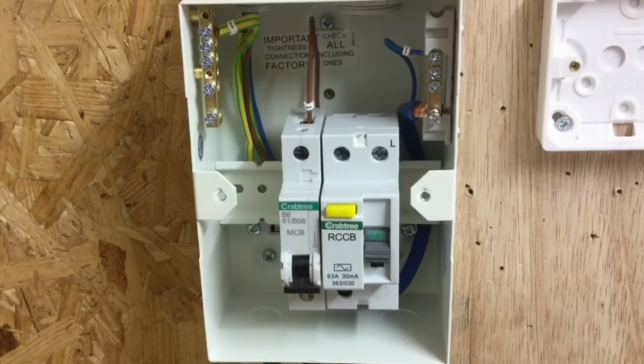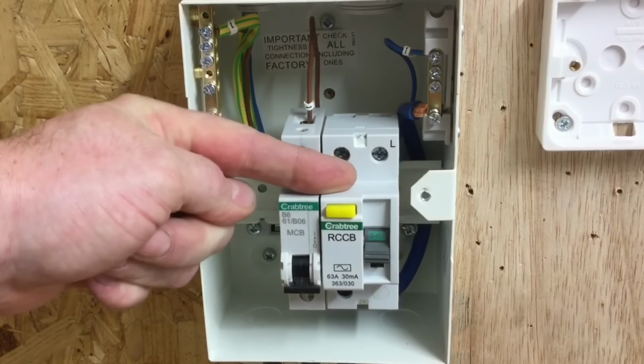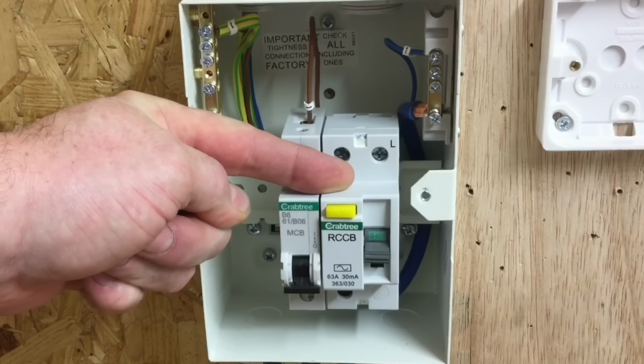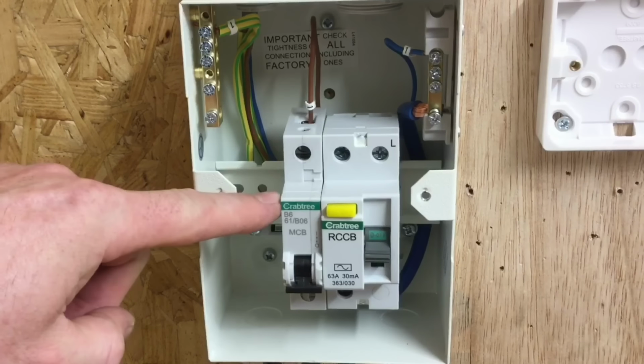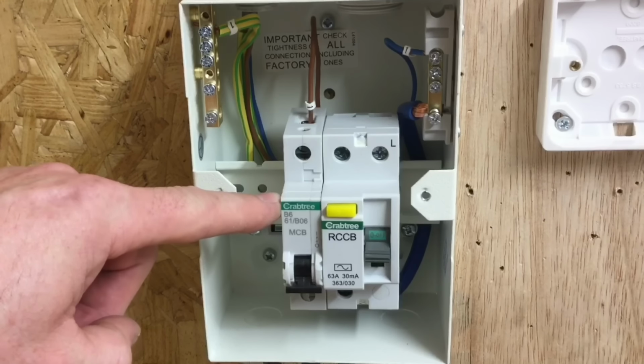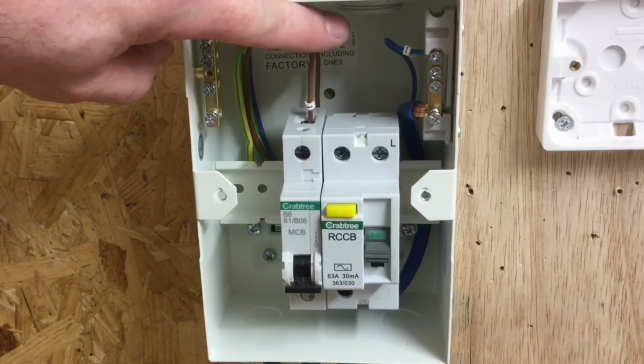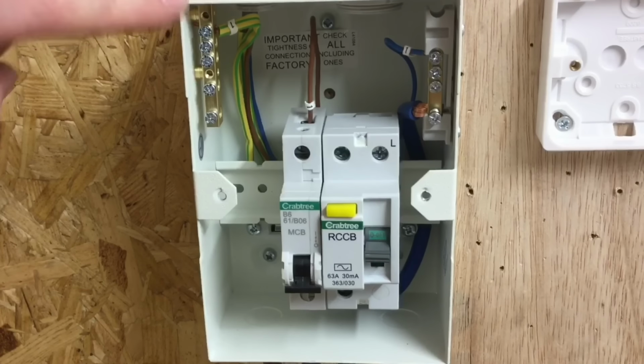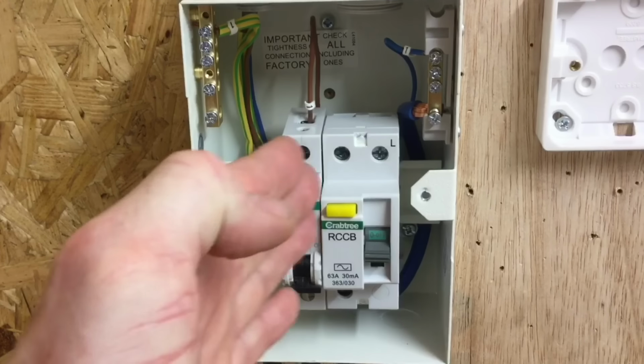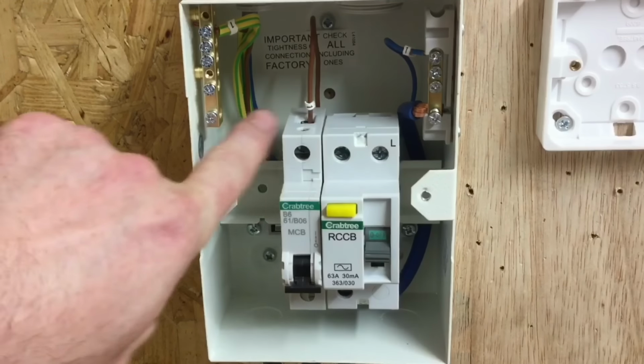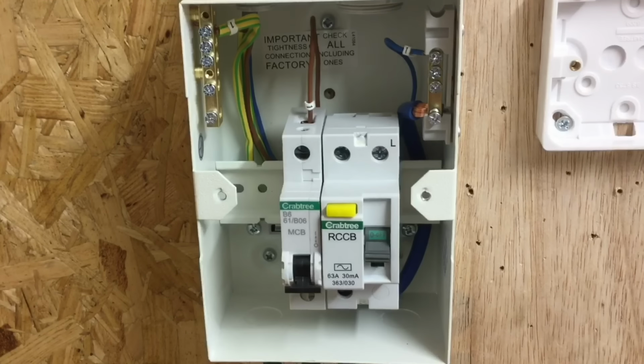So to recap then, we've terminated our 1mm squared PVC twin and CPC cable for a lighting circuit into our two-way metal clad domestic 17th edition Amendment 3 consumer's unit or distribution board, whatever you'd like to call it. We've got additional protection offered by an RCCB, rated at 30 milliamps or less. We've got a circuit breaker type B, 6 amps for our lighting circuit. We've identified the neutral, the line and the CPC with number one. It's the first circuit, it's next to the main RCCB. This would be circuit number 2 when that circuit breaker is fitted for an additional circuit.